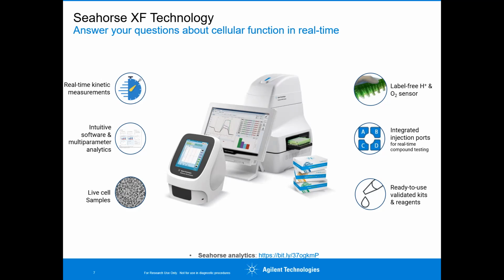Most people run a monolayer of cells, but several labs routinely run tissues, whole organisms, or spheroids on a Seahorse. And you don't need any labels to run your assays, just the sensor cartridges, which detect the two analytes, protons and oxygen. There are 4 injector ports for each well, and many of our assays use a combination of 2 or 3 compounds, leaving you with 1 or 2 ports for your compounds of choice.